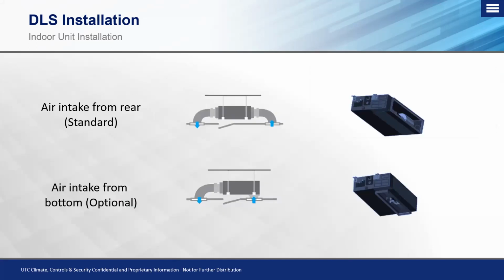So as I stated before, when we were taking a look at the picture of the unit that was hung upside down mistakenly, you have 2 options that you can do for return air into the unit. You can do a horizontal return air, or you can do a bottom side return air. And you'll see here that this panel comes with a set of Phillips screws that you can take off and remove, and you can remove this bottom panel.